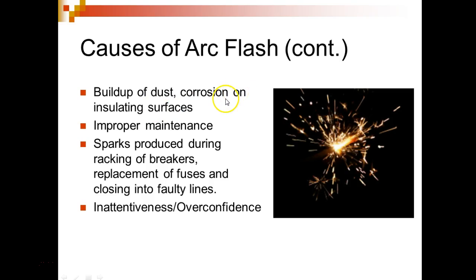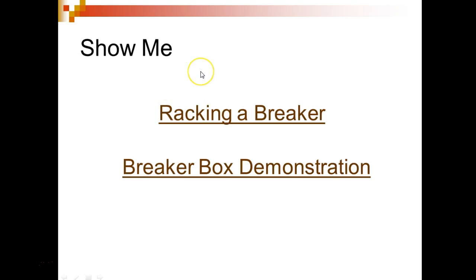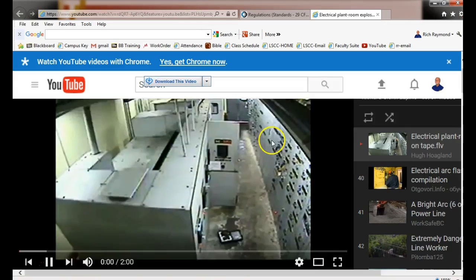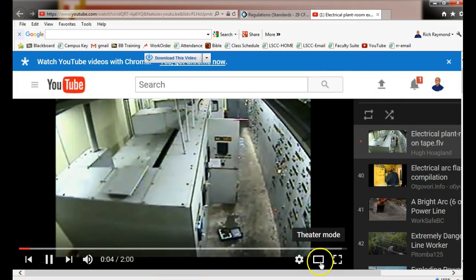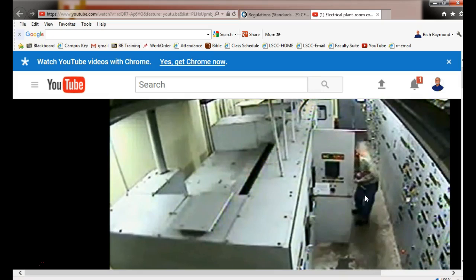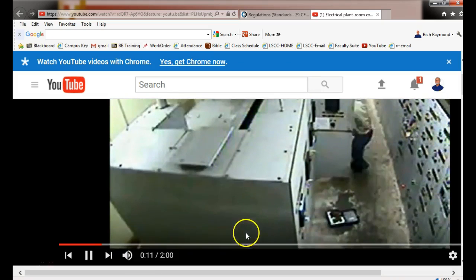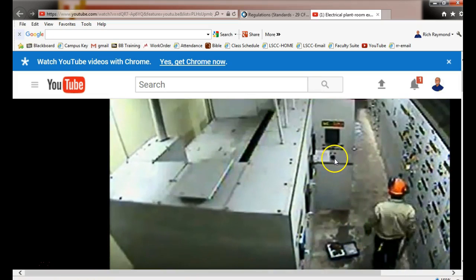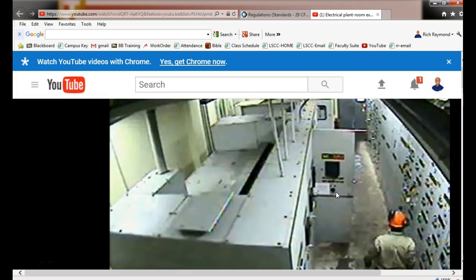Racking a breaker. When you think about breakers, you think about the breakers in your house. When we get into industry, we're talking about much bigger breakers. So we'll see if this link works. So they're racking a breaker right here. This is a breaker box, and they've got the breaker out. Notice the hole in the door right here. What do you think that hole's in the door for? So they can rack this breaker, or insert it, into the panel box. This breaker is so big that they put it on rails and literally crank it in, and the connection is made in the back.